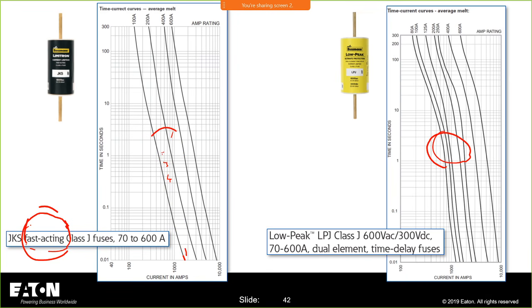So with your fast acting fuses, you wouldn't use this fuse on a motor or a transformer primary. Data centers love these fuses. They eat them up. Why? Because they don't give you any room for time delay on any of those currents, because you don't need it in some of those applications. And then your class J's, your LPJ as opposed to your JKS, your LPJ is going to give you some time delay, and that is good for your transformer inrush currents, your motor starting.